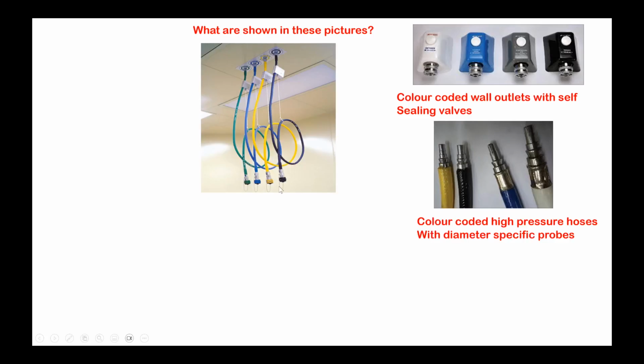And what is this? Again, high pressure hoses delivered from the ceiling. So this is called the ceiling pendant or the ceiling gas outlet. This is the wall outlet, which will be at a reachable height. What is the purpose of hanging them from the roof instead of connecting them to the wall? Just logical thinking. If it is connected to the wall, how will it go? It will lie on the floor before it reaches the machine, whereas here it can directly drop down. So tripping can be avoided, and the accidents in the theater are avoided by the ceiling hoses.